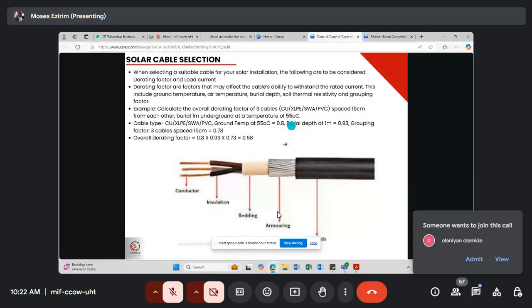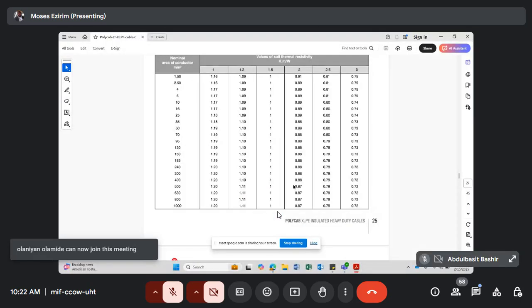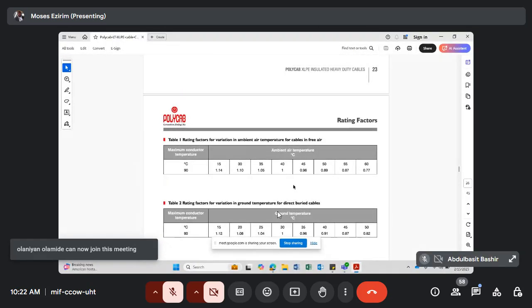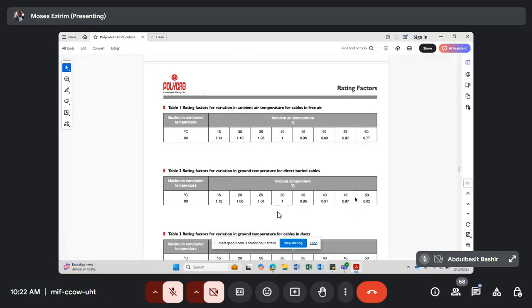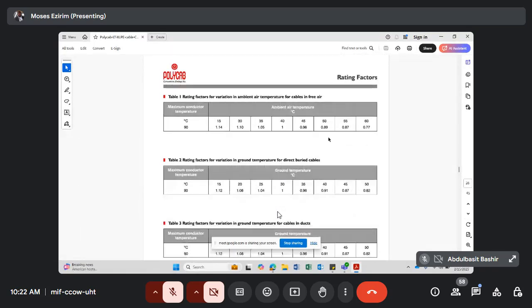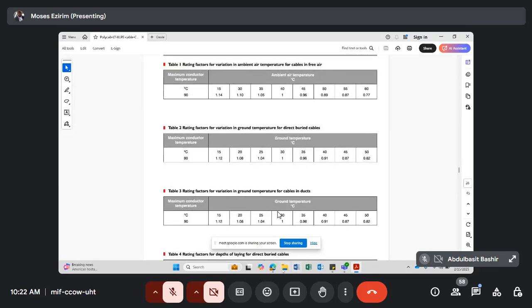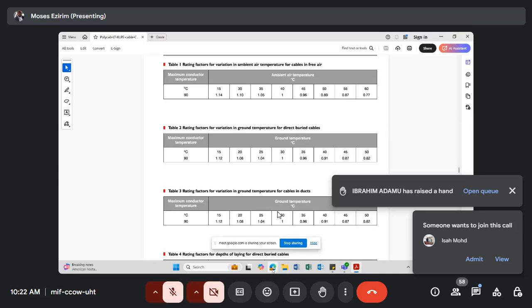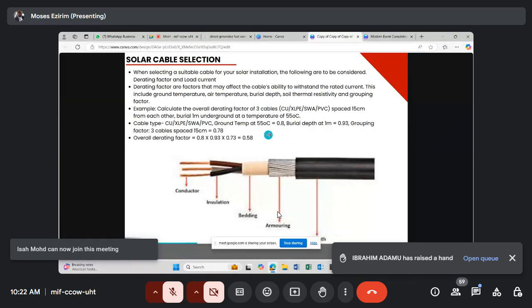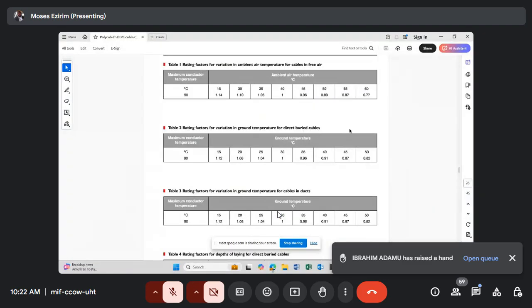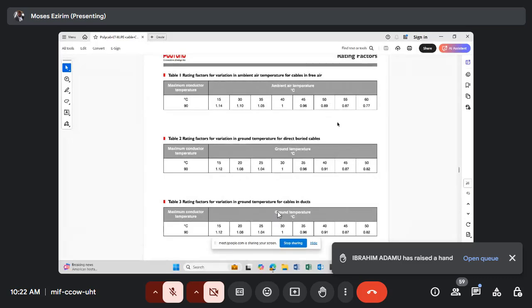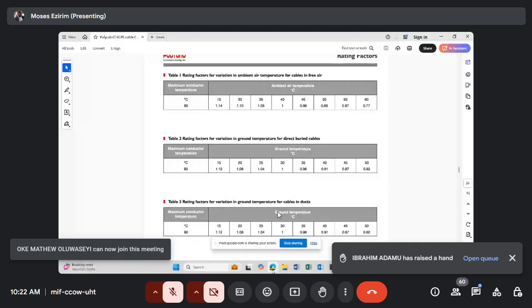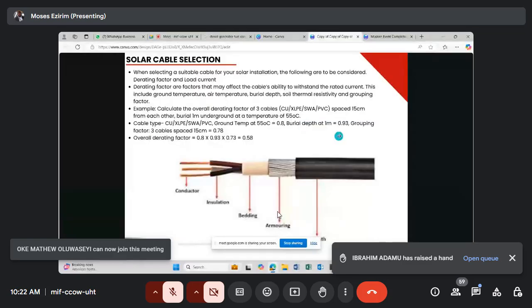The ground temperature for 55 degrees Celsius. Let's see if we can see that. Ground temperature, we are going to bury it under the ground. Let's see the temperature for 55 degrees Celsius. All right, so for 55 degrees Celsius, the ground temperature factor is 0.8. This catalog does not factor it, so you can use a catalog that does. So now let's see, then the burial depth is 1 meter. This would be the derating factor.